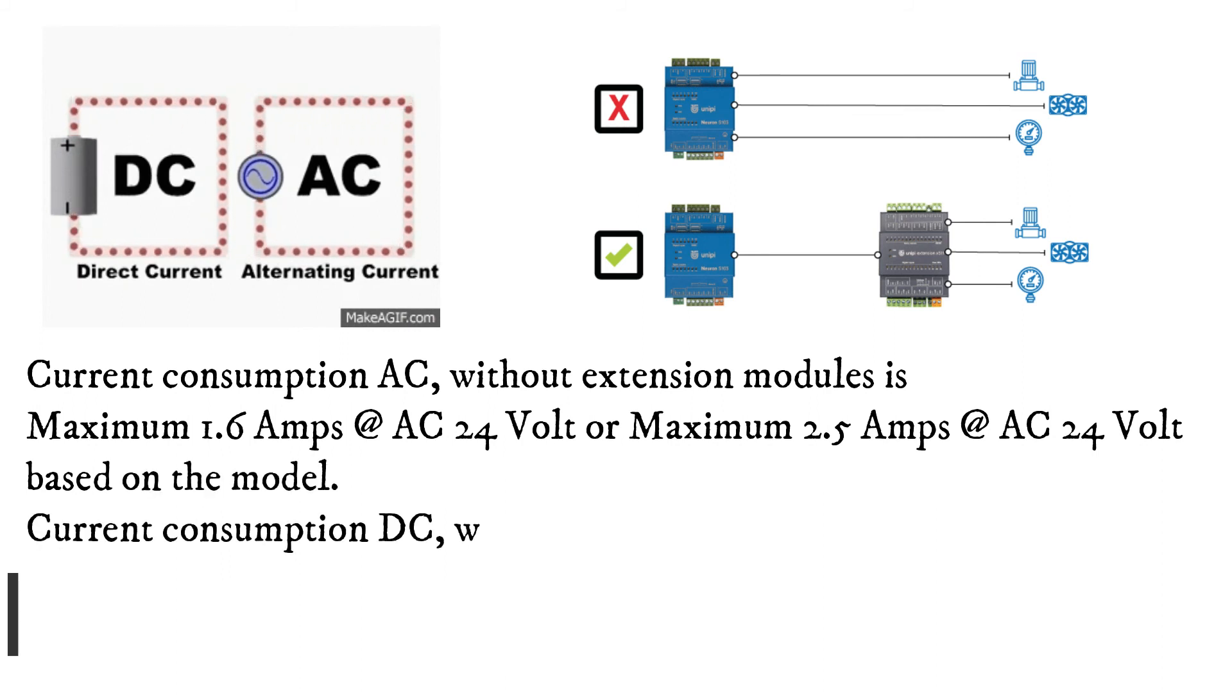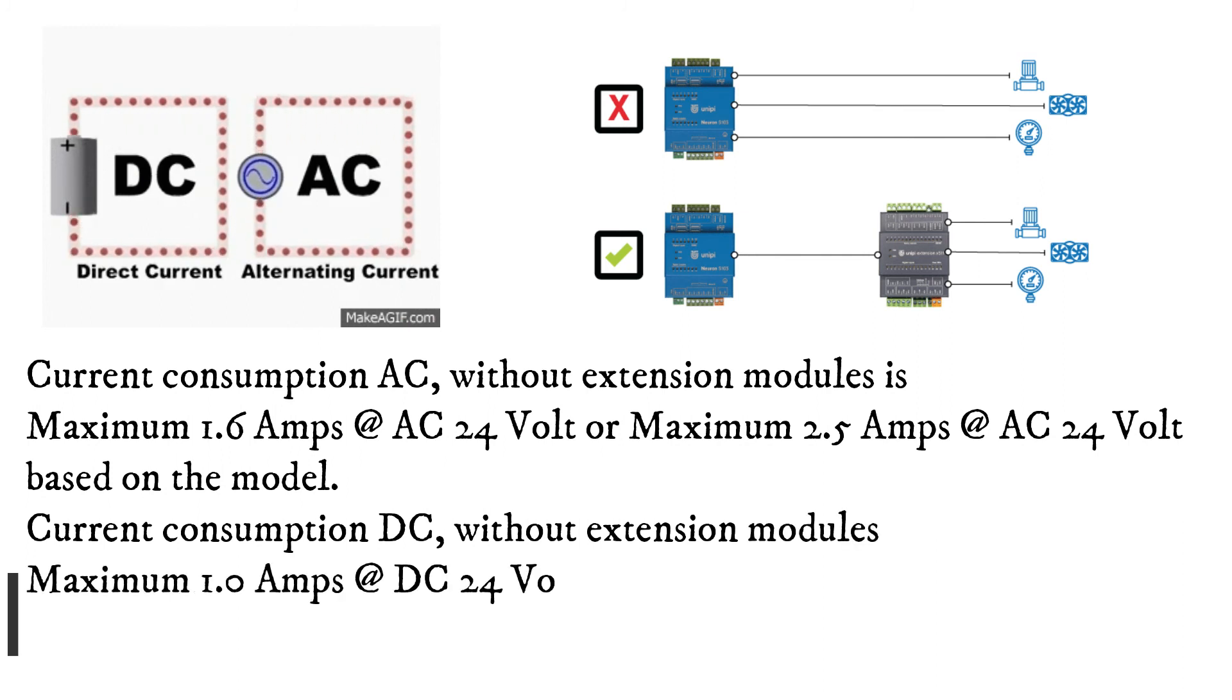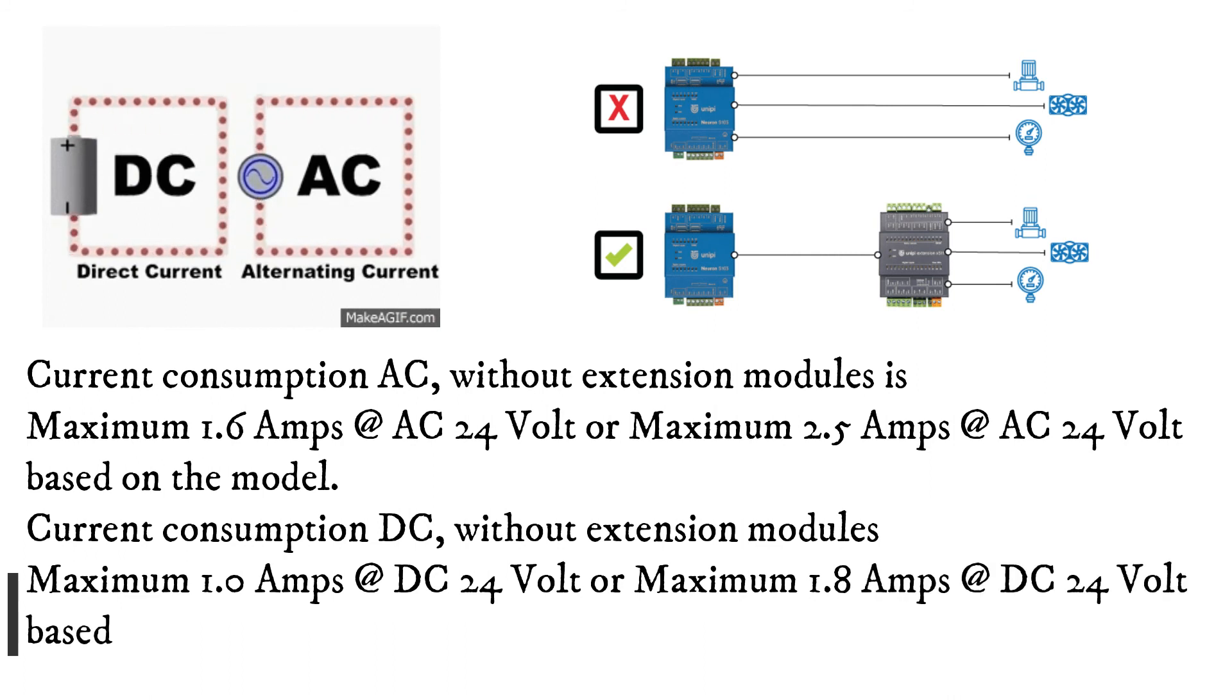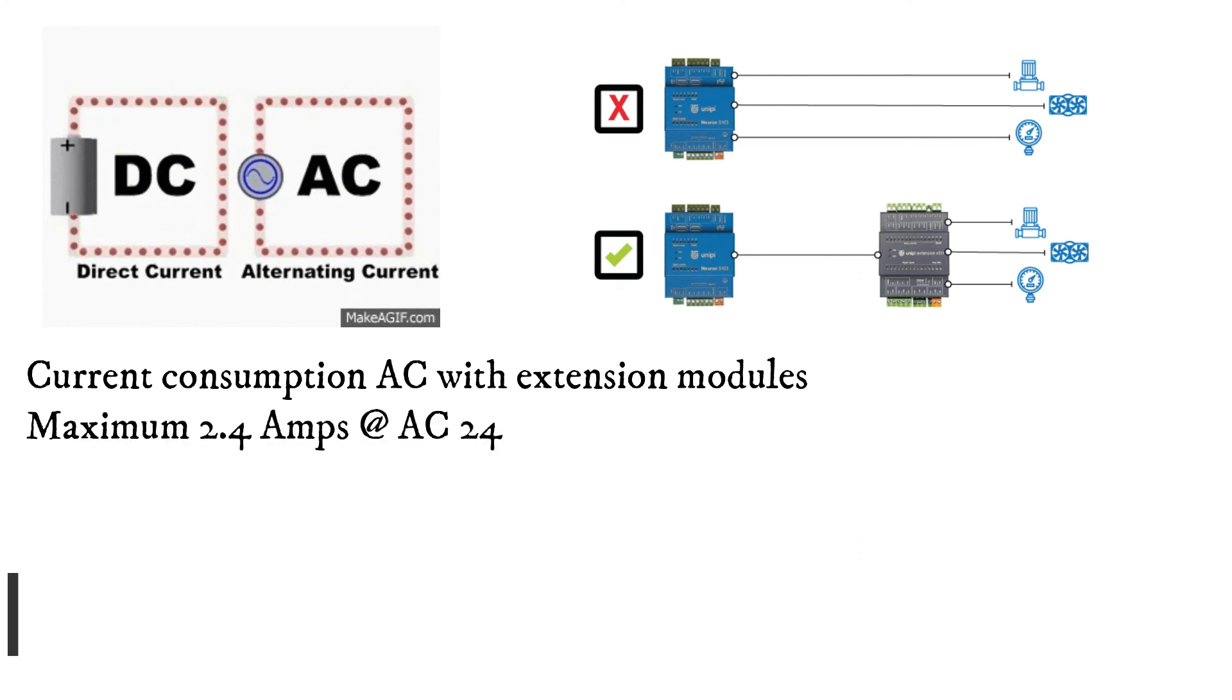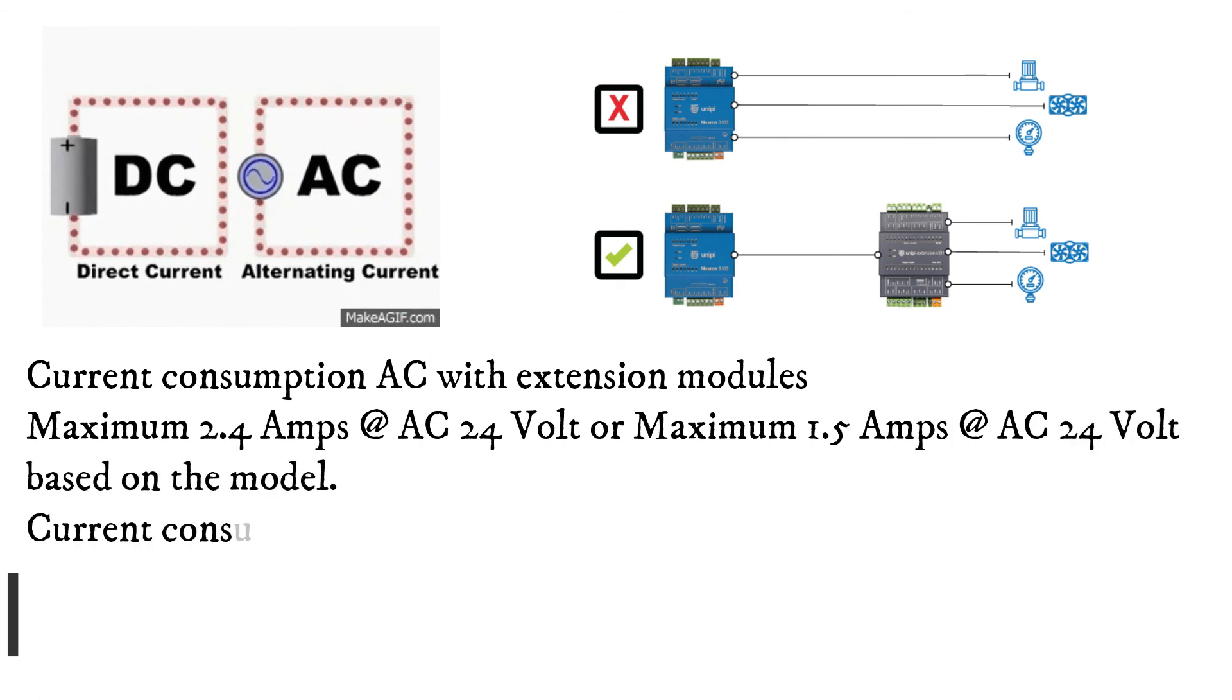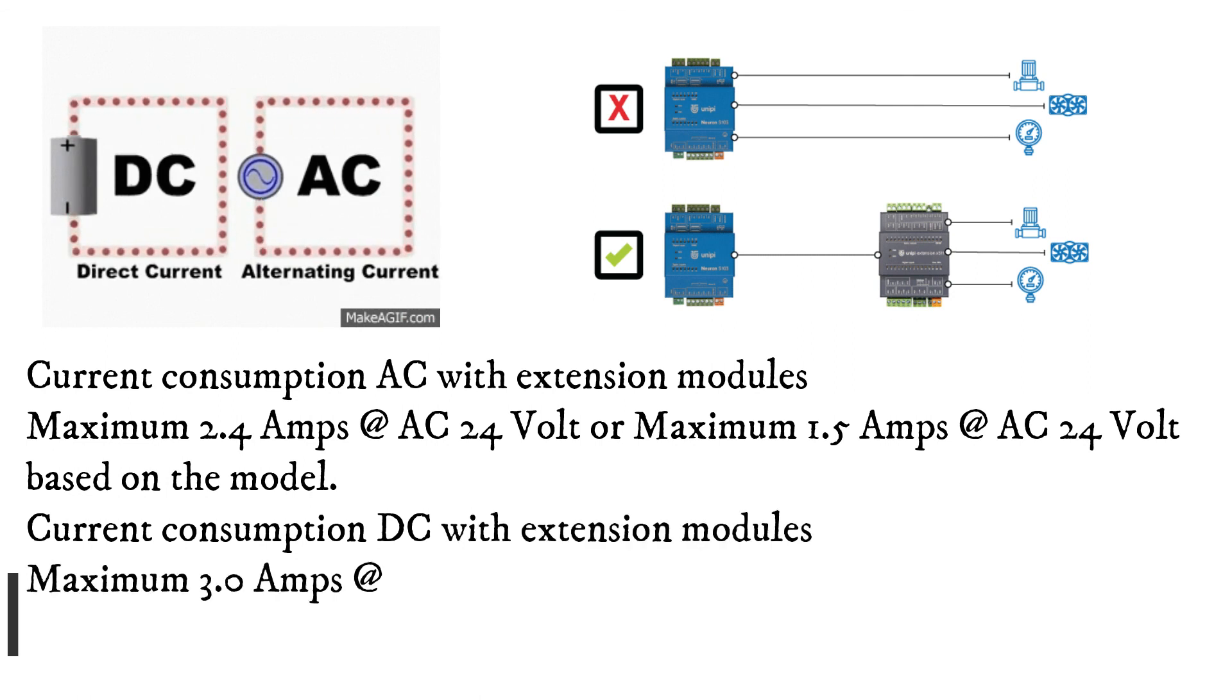Current consumption AC with extension modules: Maximum 2.4 amps at AC 24 volts or maximum 1.5 amps at AC 24 volts based on the model. Current consumption DC with extension modules: Maximum 3.0 amps at DC 24 volts or maximum 2.2 amps at DC 24 volts based on the model.